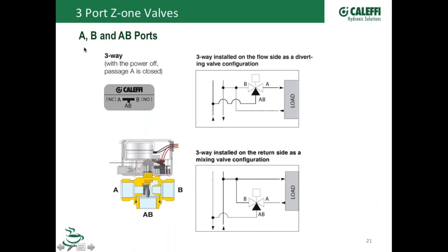Yeah. Now, also, we do have a couple choices for three-port zone valves. Now, here's a valve. Notice on this valve, there's three different markings on that. You've got an A port, a B port, and the AB, which is a common port.